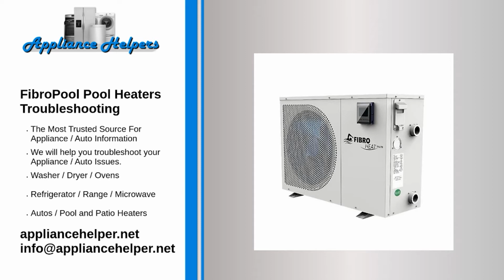Are you using the low settings on your variable speed pump? For operation, heaters require a minimum GPM flow. If you are running your variable speed pump on the low setting, make sure you meet the minimum GPMs for your heater.